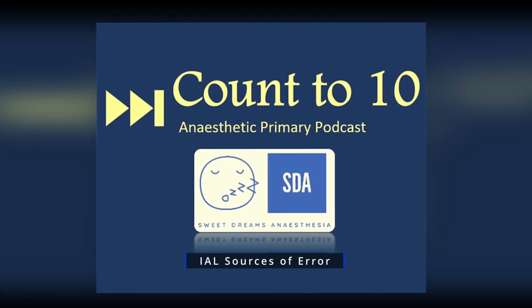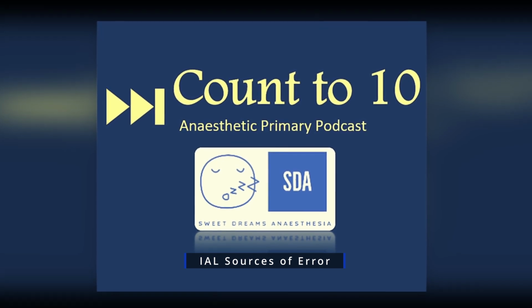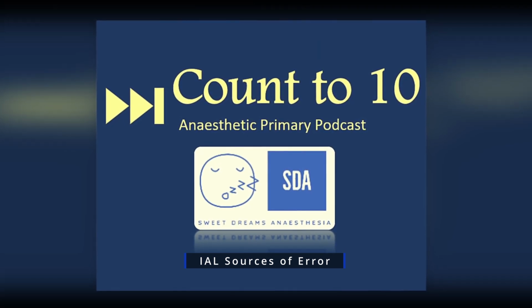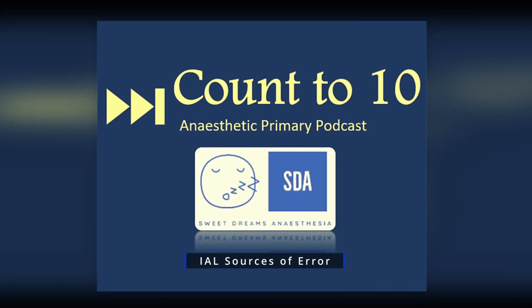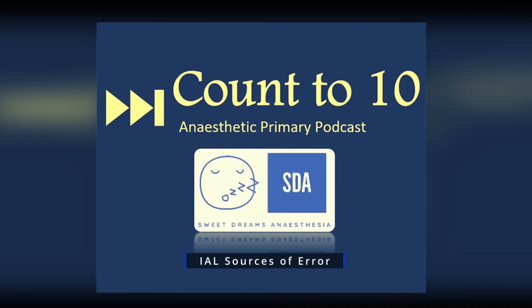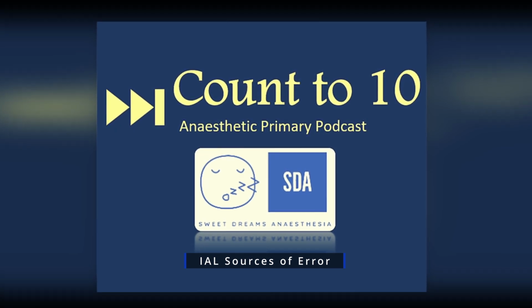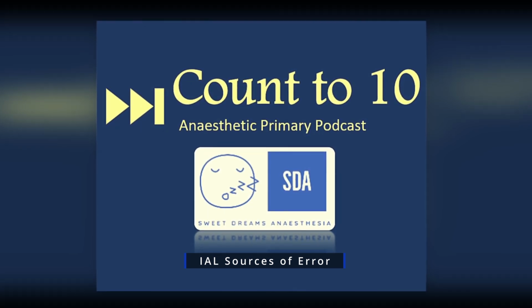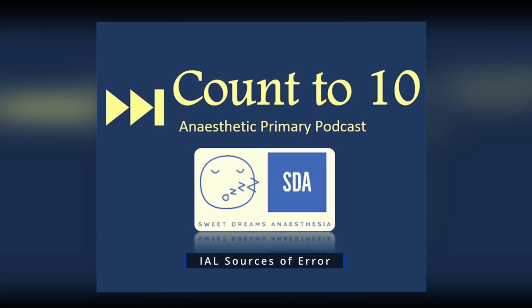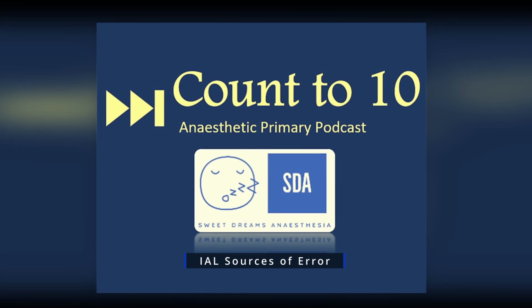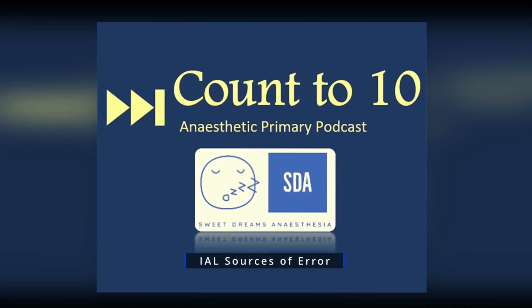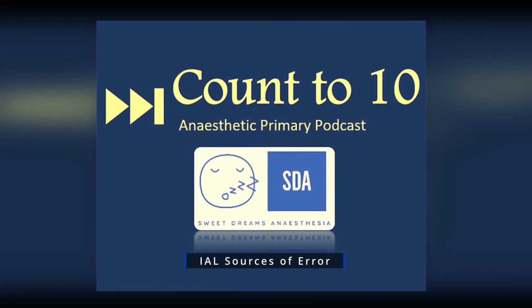Now, in order to make sure the arterial system's natural frequency is high, there's a few things we can manipulate, and this is based on the equation to work out natural frequency. By no means do you have to know this, but there are a few important numerators and denominators that we manipulate in order to get a high natural frequency. These involve ensuring that the width of the tubing is no smaller than 1.5 millimeters, because smaller width will decrease natural frequency. Another factor is the length of the tubing. Longer tubing decreases the natural frequency.